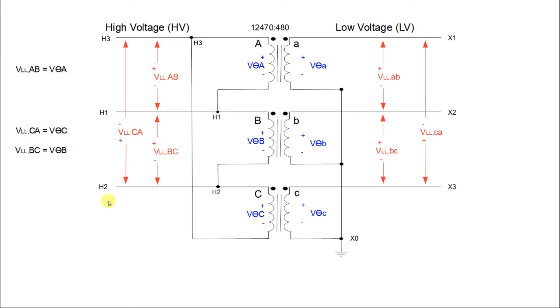So we can make a statement that for a delta-connected transformer, the voltage across two lines shall equal the voltage of the phase winding. That is true for a delta-connected transformer, and this is why in the field people get confused between line-to-line voltage and phase voltage. That's why it's important to be able to read the faceplate on a transformer and know how that transformer was connected.